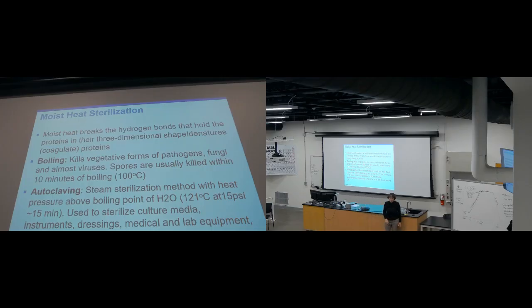There are also settings when it comes to sterilization, because this pressure has to be released, so the steam has to go through a series of pipes to release the pressure. Sometimes you want to release this pressure out of the autoclave fast and sometimes slow. You want to let it go slow when you are using media, because in this case it can evaporate really quickly. So you use a slow exhaust for liquid.